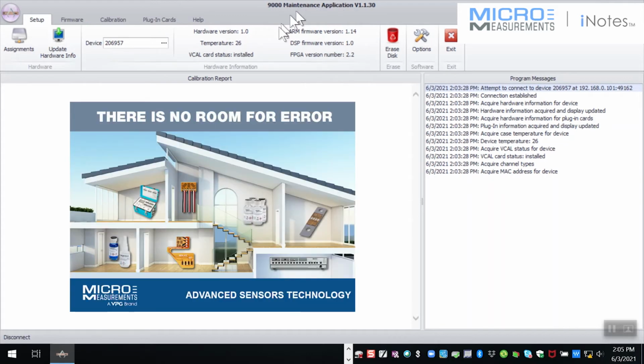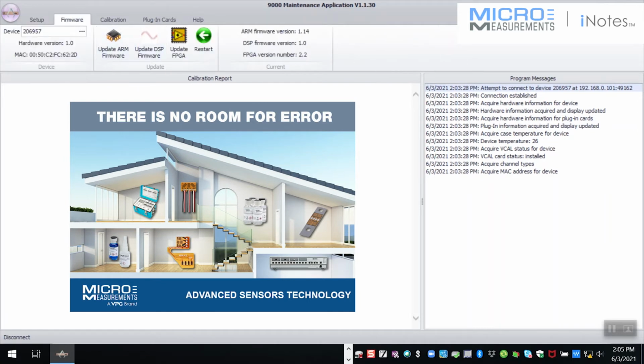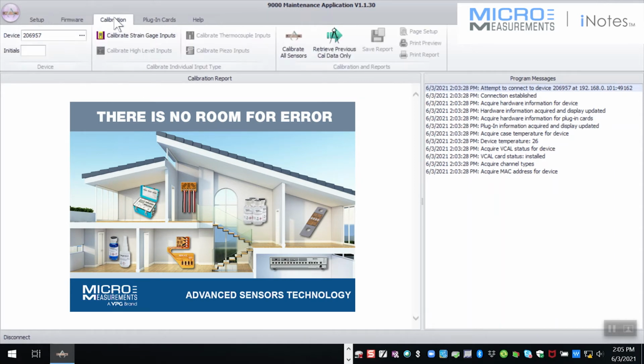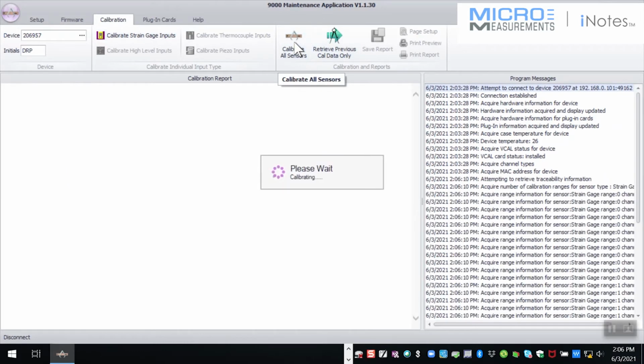Yep. So one of the things that gets reported back here is my firmware versions. If I find out that maybe something's out of date, maybe I need to upgrade them, there's a tab here that walks you through that for each of the scanners. And then jumping over to what we were just talking about, probably should have gone there in the first place, an opportunity to perform a system calibration. So all it really wants is some kind of initials for whoever's doing it, and then you can tell it to perform that system calibration.